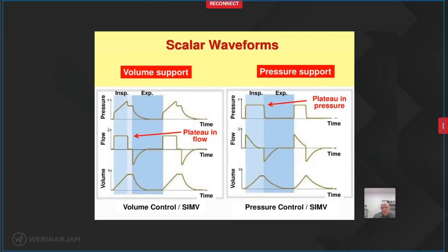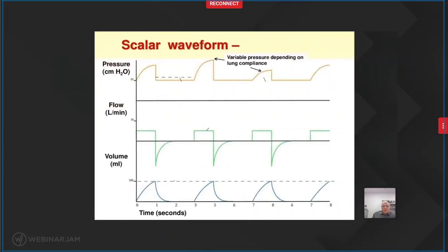Okay, so again, putting everything together here, on the left side, we have the three waveforms during volume support. As you can see, the sinusoidal shape of the pressure waveform, the square flow with a plateau, and the volume. On the right side, we have the pressure support in which the plateau now occurs during pressure. Okay, the pressure waveform now is square or boxy, and the flow takes the shape of a decelerating flow. Okay, so this is basically the same thing. This, unfortunately, I guess I lost my animations.